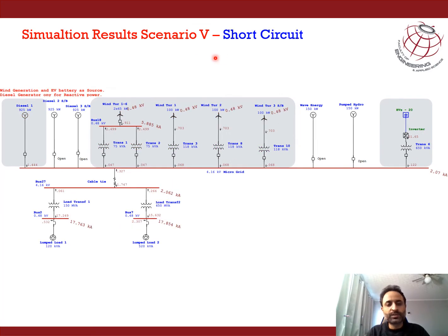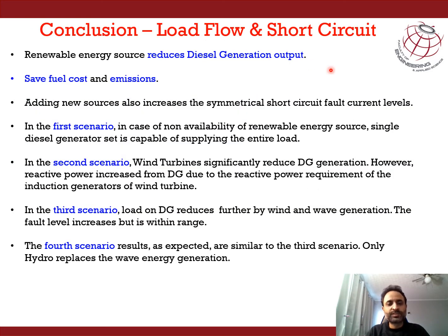The short circuit values for case 5 are also within the limit of 25 kiloampere, because of the slight addition to the fault level by the EVs. So if we come to the conclusion of these studies, load flow and short circuit, we see that renewable energy will result in a reduction of the diesel generation output, and hence will result in saving of fuel as well as a reduction in emissions.